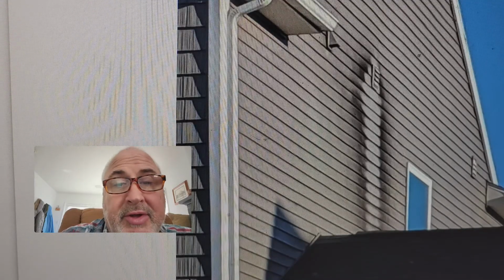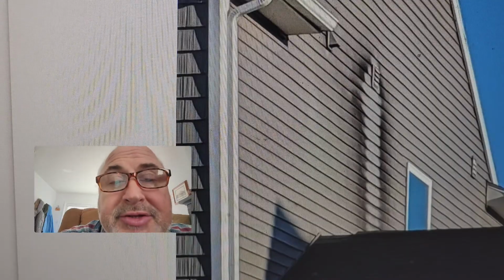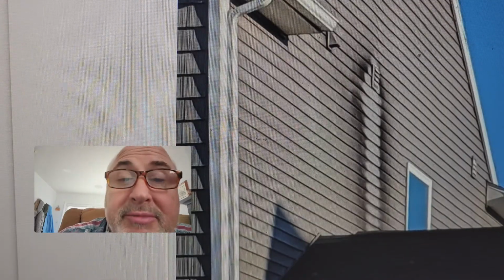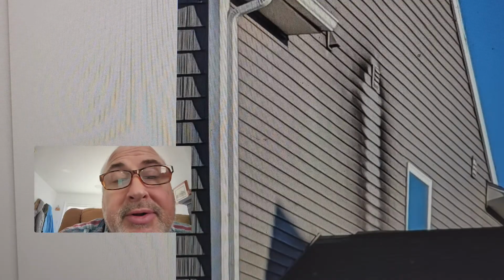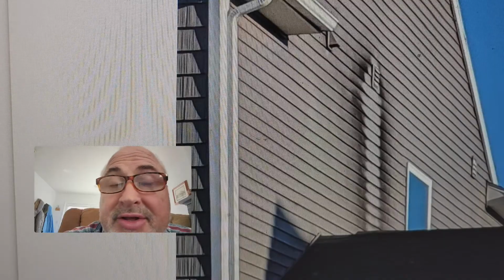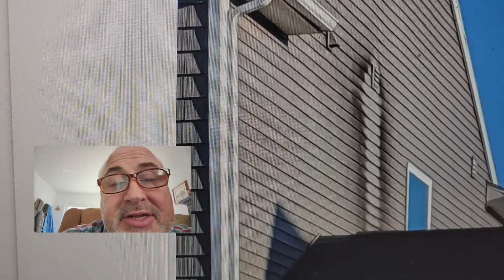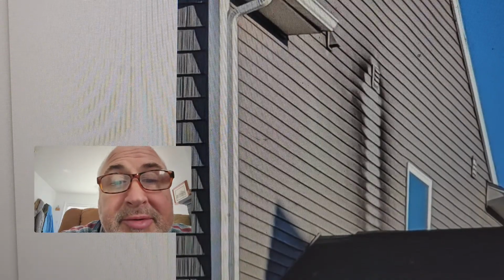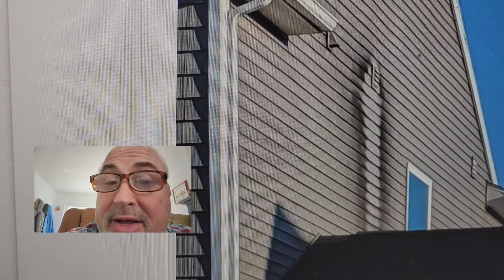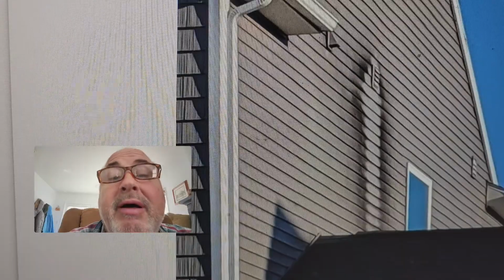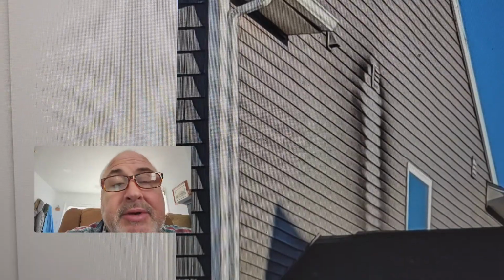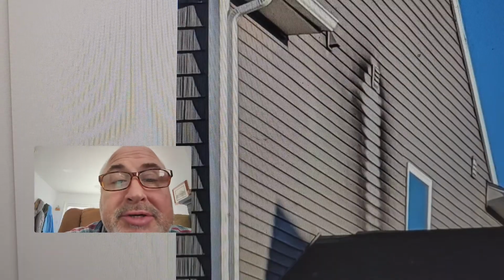So if you've got negative pressure because your cold air return in your basement has duct leakage, in other words, you have a cold air return register in your basement, or you close your basement door and your cold air returns aren't sealed. The way you find out is simply sit at the bottom of the door in the basement, put a piece of toilet paper there, and if everything gets sucked down, you've got negative pressure. You probably have radon gas. You're sucking moisture out of the sump pump. All kinds of problems. So that starts off with an imbalanced heating system, which means your upstairs is positively pressurized.